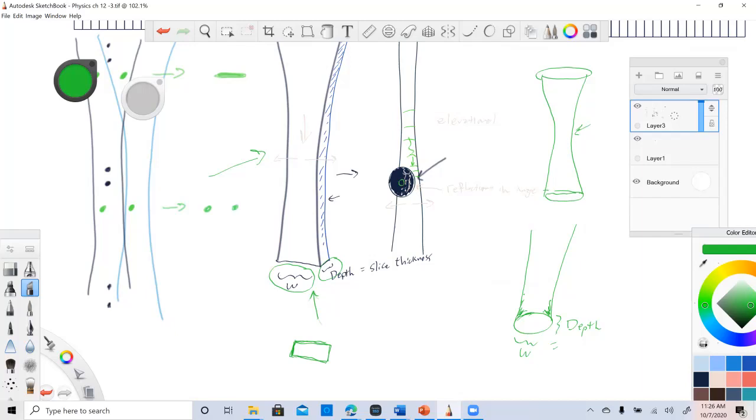I believe it does, but with array probes, an acoustic lens is used to create a thinner slice. So an acoustic lens, we've learned so far that we can, on the older transducers, or maybe the single element transducers where you can't control with multiple elements, put an internal or an external lens on.